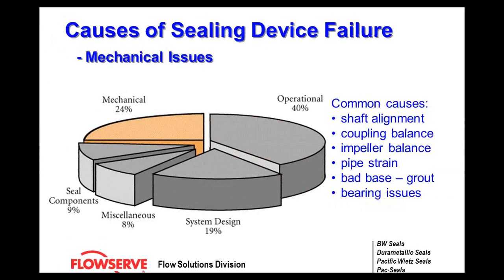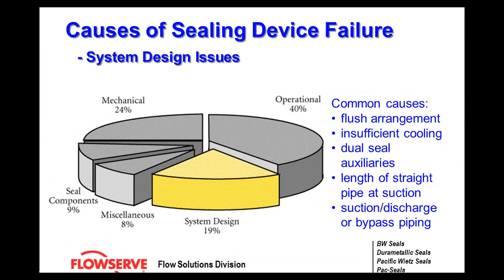Some common causes of mechanical failures: shaft misalignment, coupling balance, impeller balance, and pipe strain. Pipe strain is a hidden killer — you build up a pump, everything is fine, but then in the plant you have to use a come-along to straighten out the pipe runs to get them to bolt up. This imparts a lot of strain into the pump and can cause real havoc with a mechanical seal. A bad base — is it grouted properly, do you have a soft foot, loose bolts — and bearing issues, as tolerances wear out and open up, also lead to mechanical seal failure.